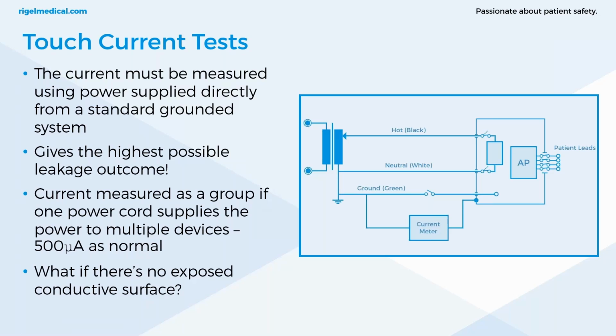It states that if a fault were to occur within the ground connection of the power cord, then the sum of the currents from each individual device would flow to Earth via any human contact with a chassis. So the touch current is measured as a whole. And that grouped limit is 500 microamps as normal. There are some suggested methods of lowering the sum leakage if you're getting higher values, and that's just done by separating the device grouping and testing them individually. But it's only required if the values exceed that 500 microamps on one power cord. So you're only doing that as an investigative method.